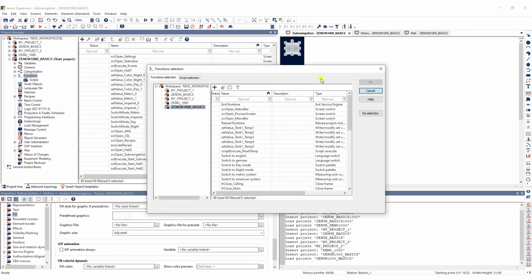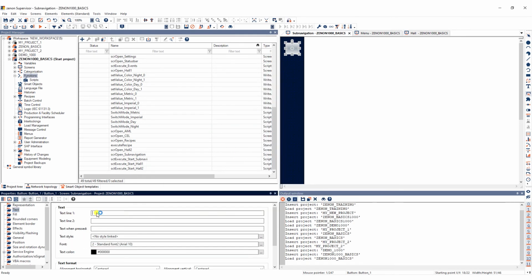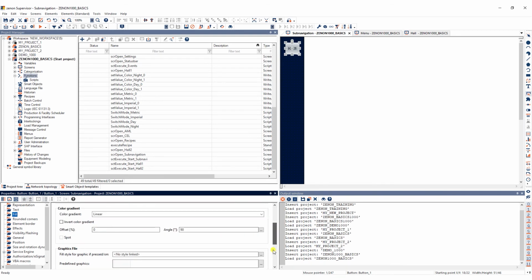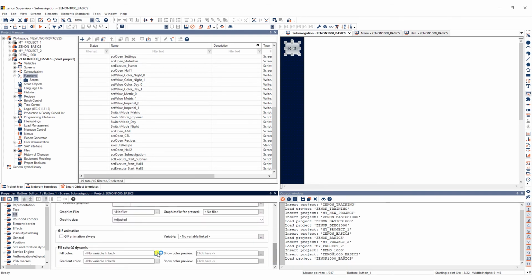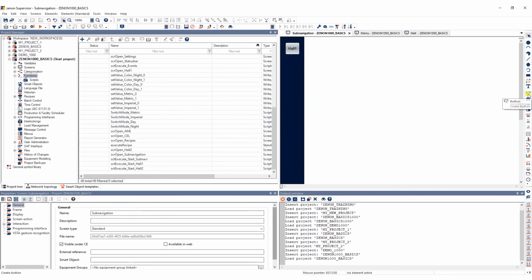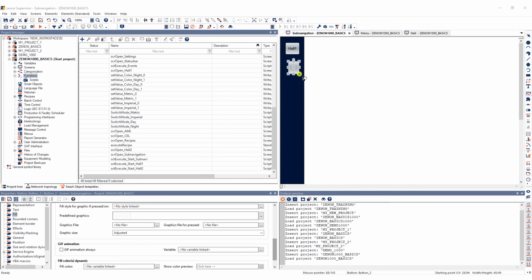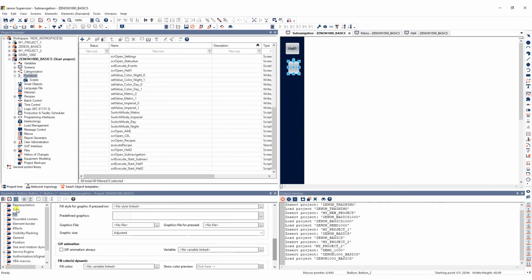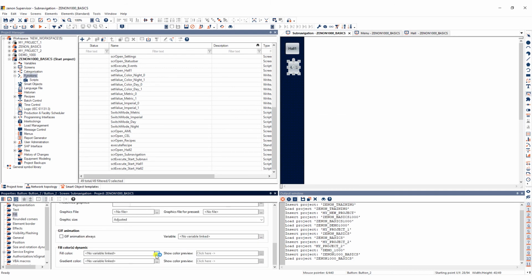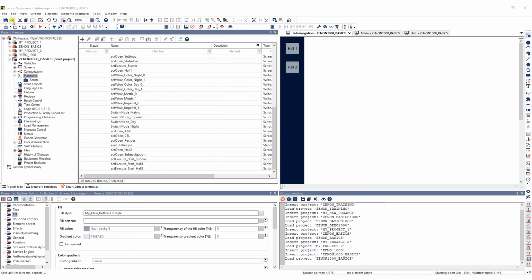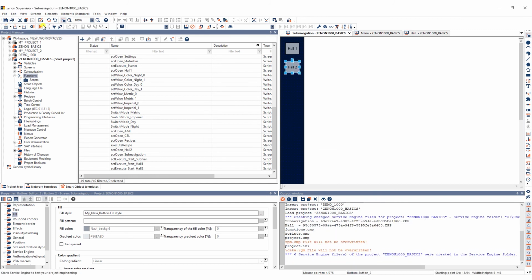In the dialog, link it to the appropriate script. In the Properties window, rename it and under Fill Colors Dynamic, select the Screen Active variable associated with Hall 1. Repeat those steps for the Hall 2 button, making sure you select the correct function and Screen Active variable. All you have to do now is save and compile the project and start the service engine.